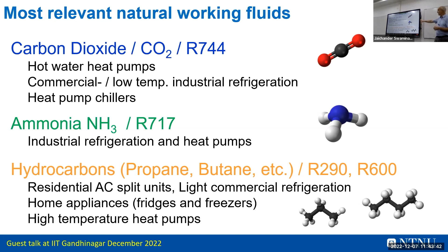This is just to show you a little bit of the properties. When it comes to CO2, you see that the pressure is relatively higher than with the other fluid, R22, the previous one, where we are quite low on pressure, while here we are 10 times more. You see at 0 degrees, we had 35 bar in CO2. But these are actual numbers, not logarithms of those. Yeah, so the evaporation pressure corresponding to temperature means at 0 degrees, when you evaporate, it's 35 bar, while for the others, it's much lower. It's comparable with these two, but it's a kind of another line up there. And that we have to take into consideration.